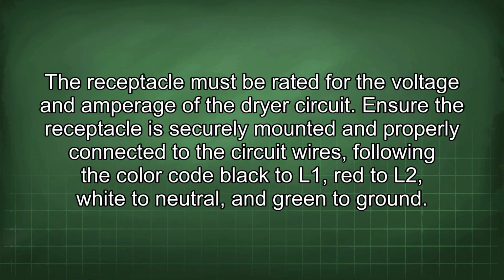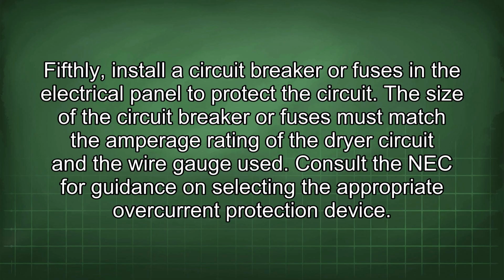The receptacle must be rated for the voltage and amperage of the dryer circuit. Ensure the receptacle is securely mounted and properly connected to the circuit wires, following the color code: black to L1, red to L2, white to neutral, and green to ground. Fifthly, install a circuit breaker or fuses in the electrical panel to protect the circuit. The size of the circuit breaker or fuses must match the amperage rating of the dryer circuit and the wire gauge used. Consult the NEC for guidance on selecting the appropriate overcurrent protection device.